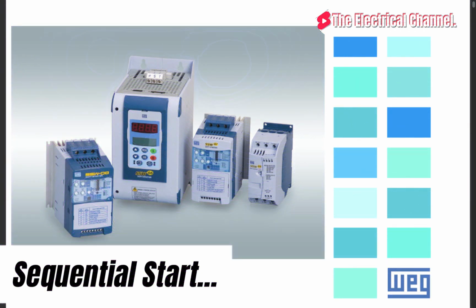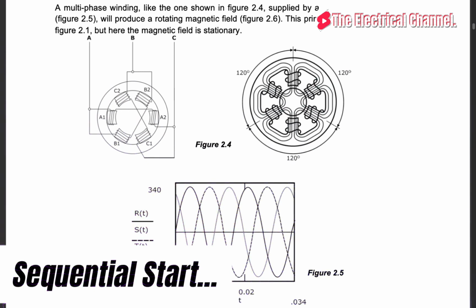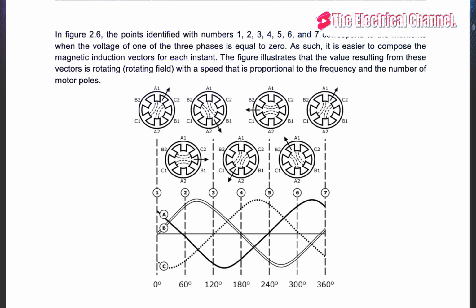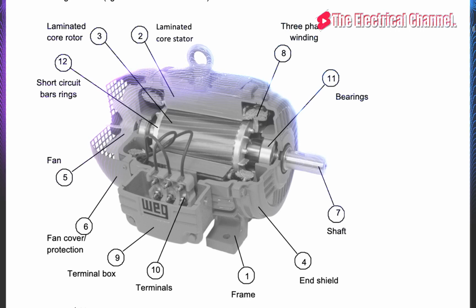Sequential start of motors. If the soft starter is going to be used for starting several motors one by one, sequential start, it is important to check that the soft starter is able to cope with the starting current for each motor during the whole starting sequence.